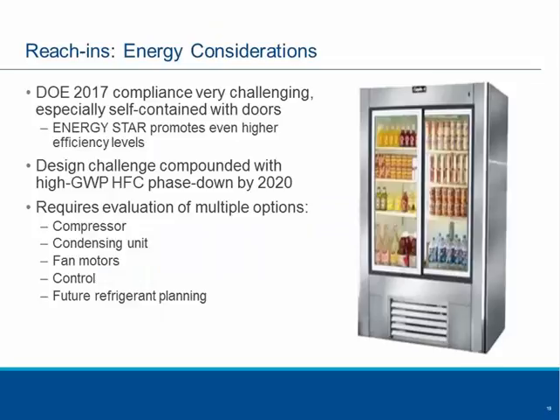The DOE 2017 compliance that Ani talked about for March 2017 can be very challenging, especially for self-contained reach-in equipment that has doors. Let me give you one example. A very typical 24 cubic foot solid door refrigerator, similar to what we were talking about in that last slide, 24 cubic foot one door refrigerator, today it has to consume 4.44 kilowatt hours per day or less to meet the minimum federal efficiency levels. If it consumes more power than that, it cannot be legally sold in the United States.